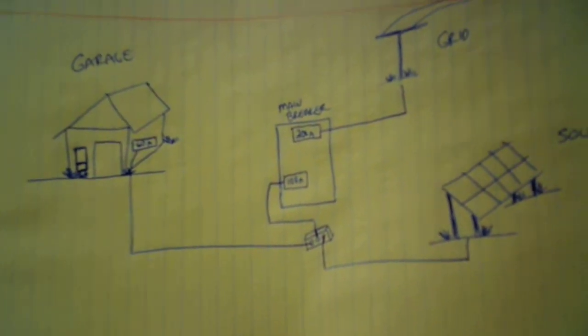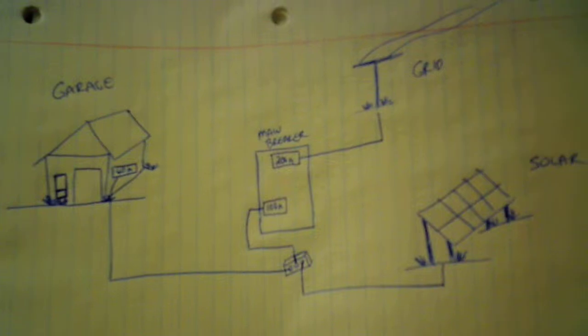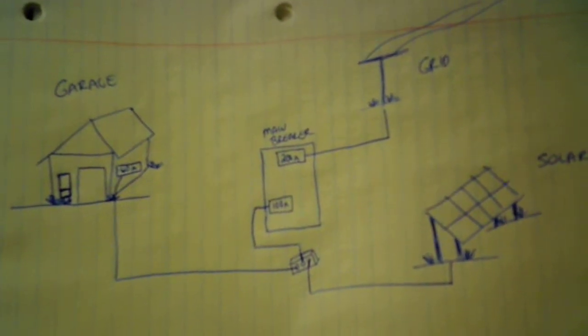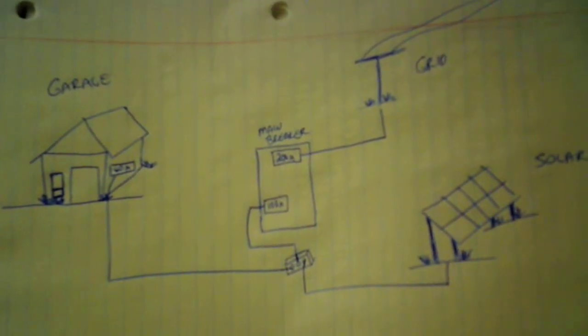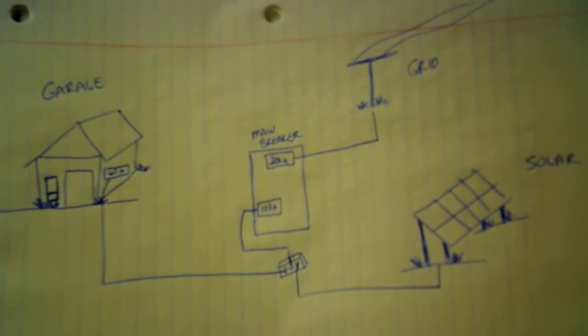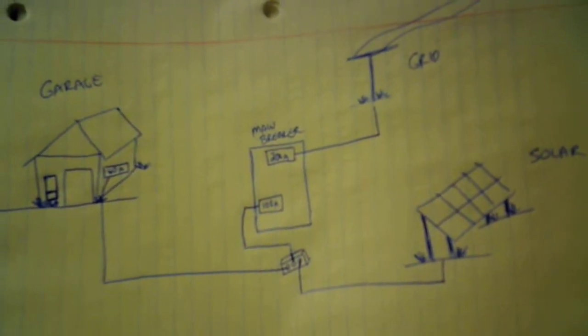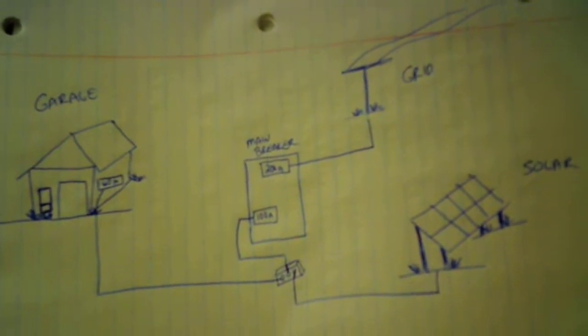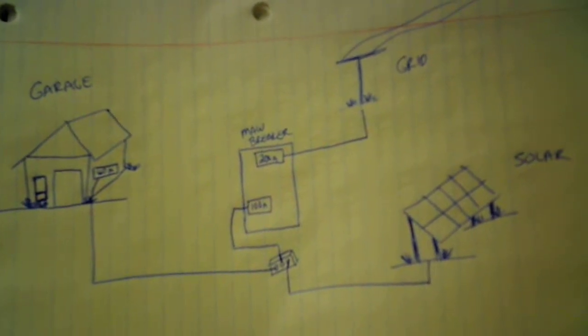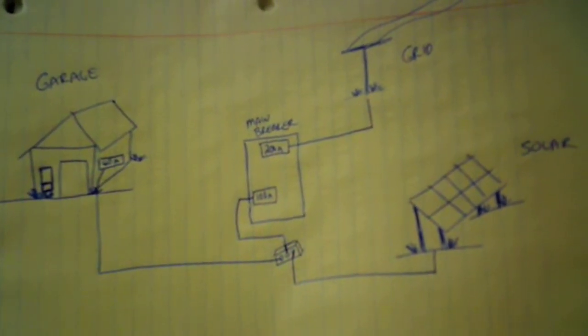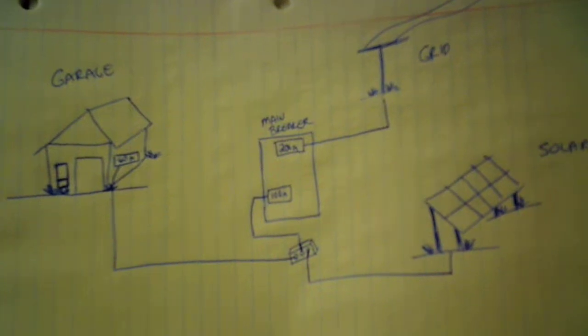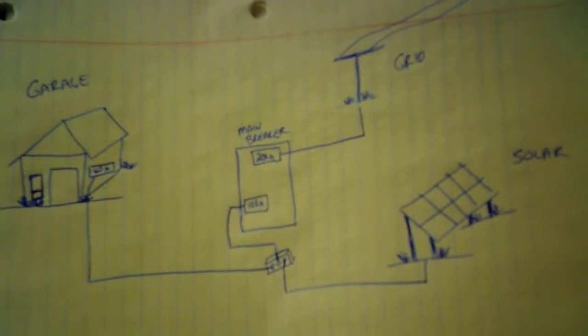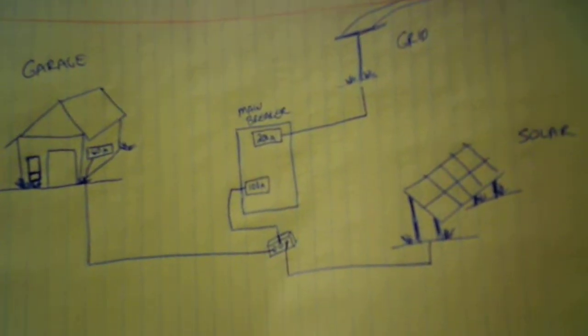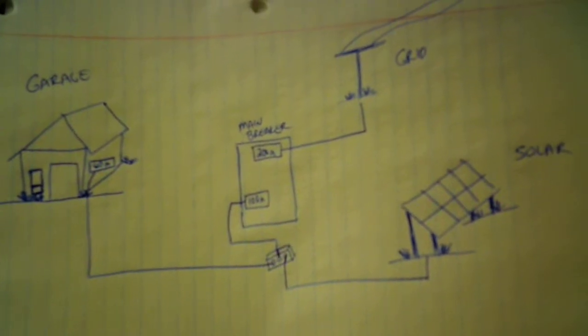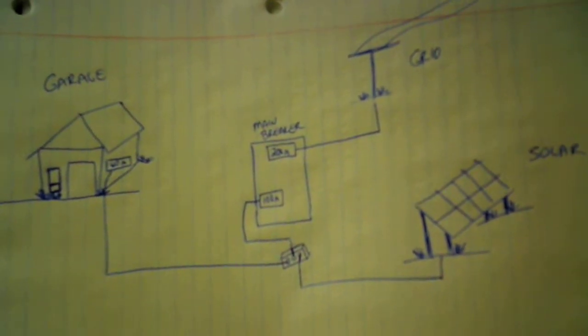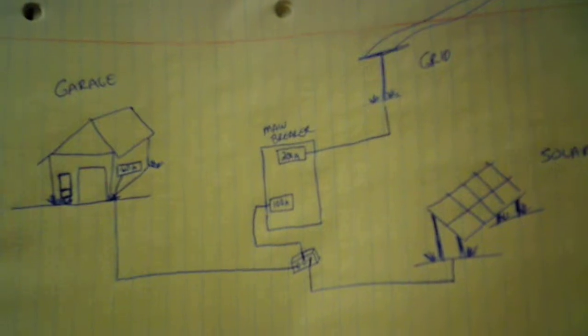I'd turn that 60 amp breaker off, have the grid 200 amp breaker on, and have the 100 amp sub-panel breaker on. That way the grid comes in through the 200 amp service, feeds the house, feeds the garage, and gives a little 60 hertz signal to my grid-tied inverter on the solar panels, so I'd still be able to have solar coming in.